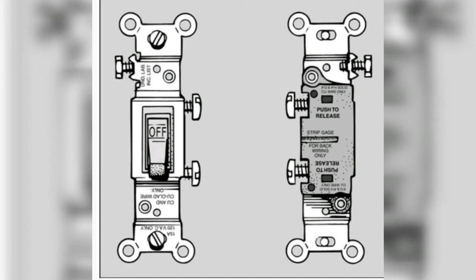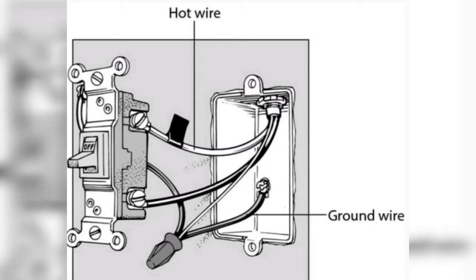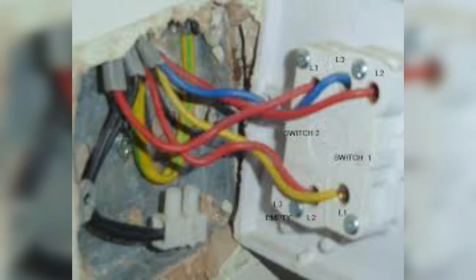Most modern switches have a screw terminal on each side and may also have a hole in the backside to accept the end of the wire. Although plug-in connections may be more convenient, they are less reliable than screw terminals, so don't use them. You can easily loosen the screw on the side of a device with a standard screwdriver, turning it counterclockwise, but you may find getting the wires out of the back of the device tricky.